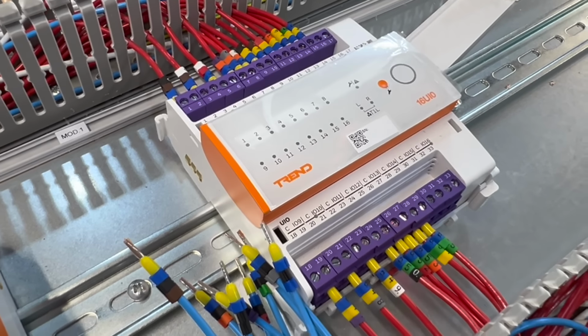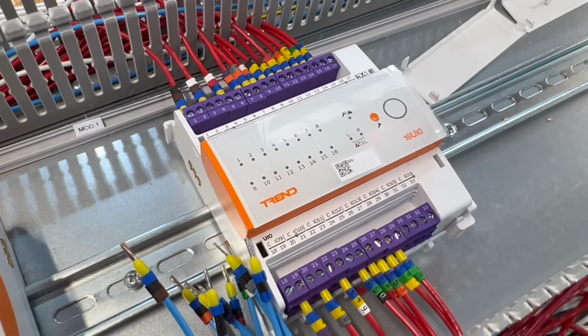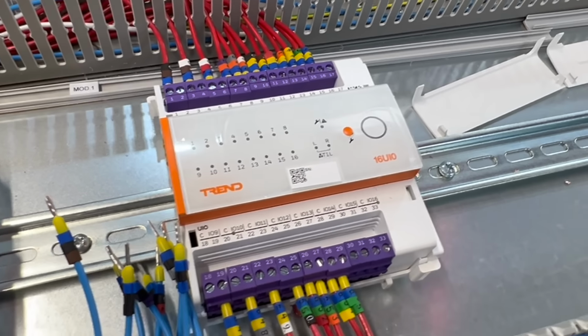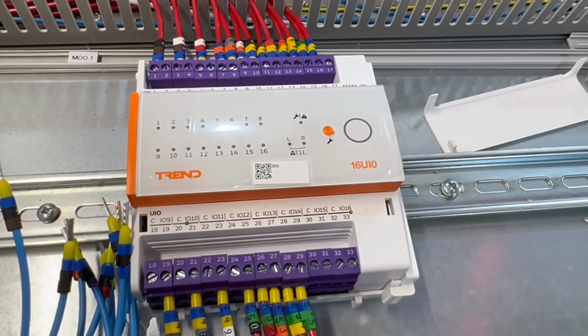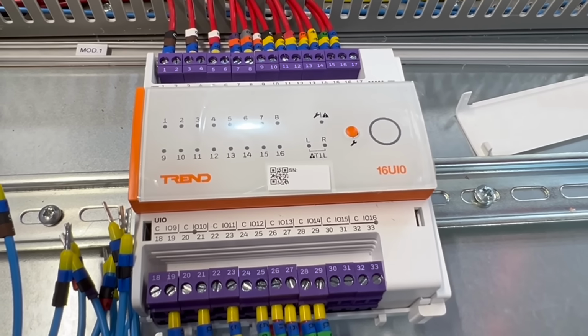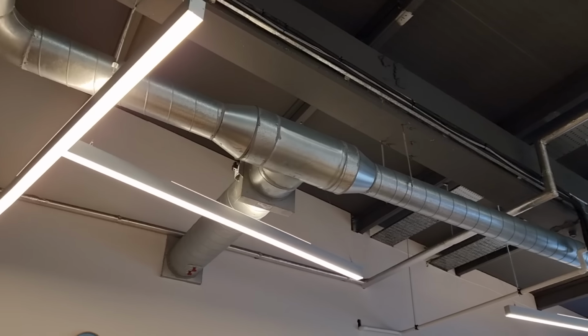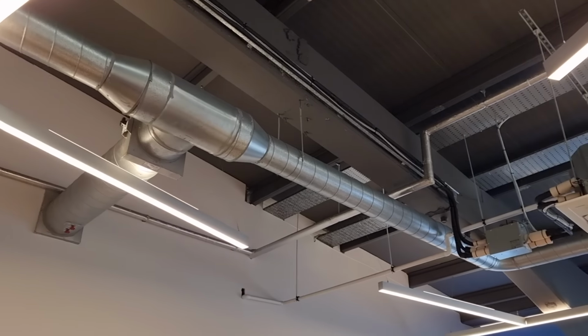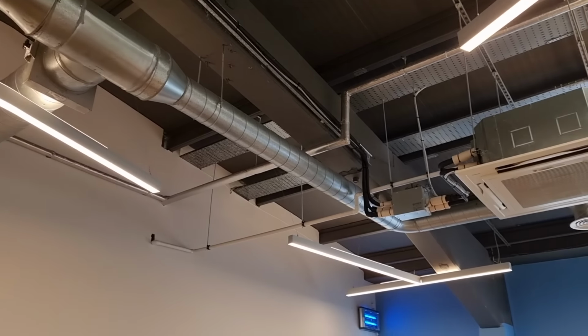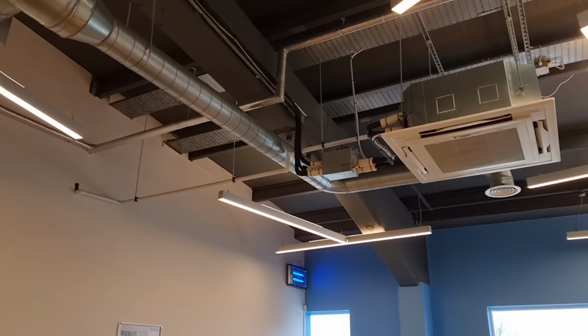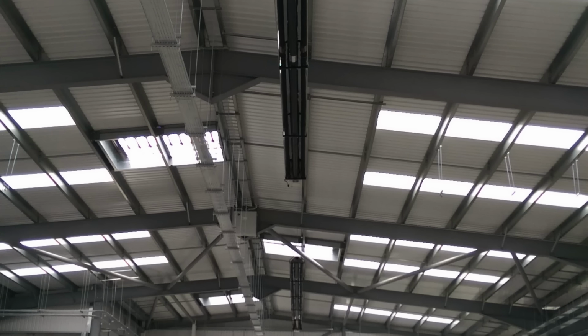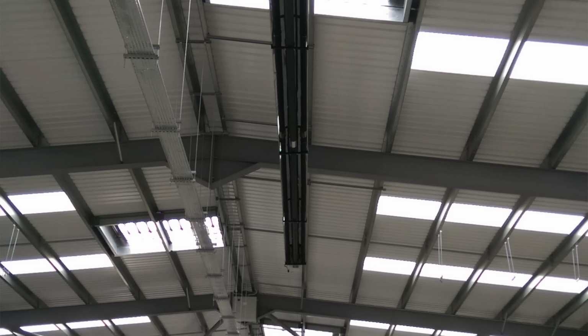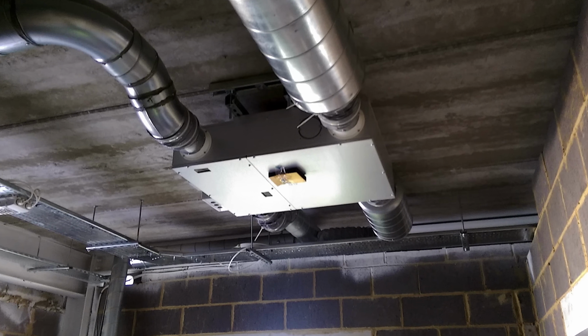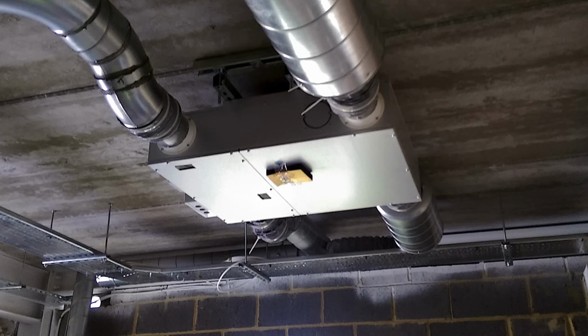So what actually is a DDC? Well, think of it as a smart little computer dedicated solely to managing and optimizing the building's environment. Instead of relying on simple on-off thermostats or time clocks, the DDC takes inputs from all over the building, temperatures, pressures, air quality, flow rates and so forth, and decides how the equipment should respond. Should the heating ramp up? Should the ventilation slow down? Should the air handling unit bring in more fresh air? The DDC works all that out and then sends the appropriate signals back out to the plant.